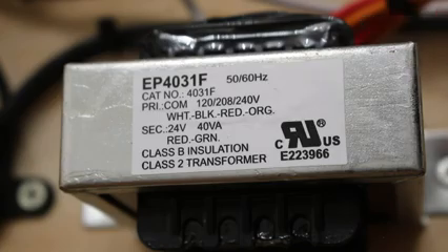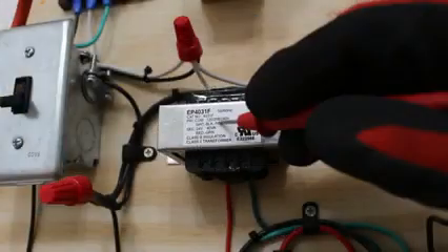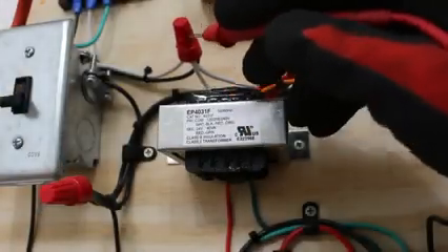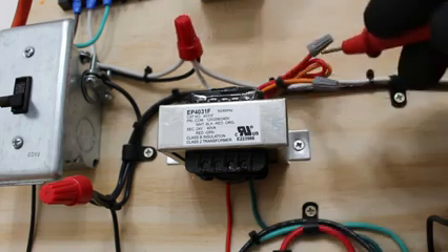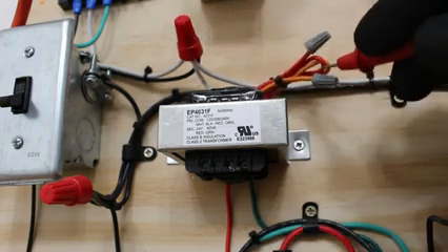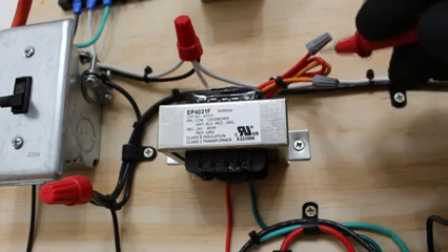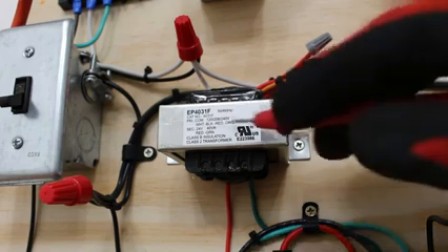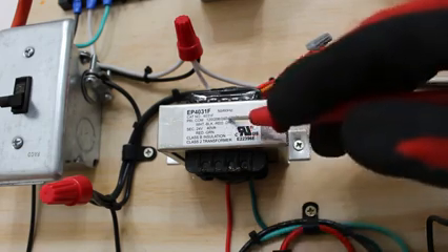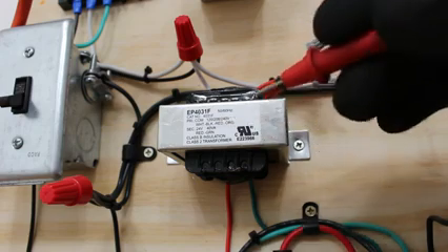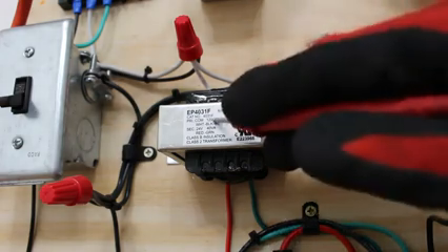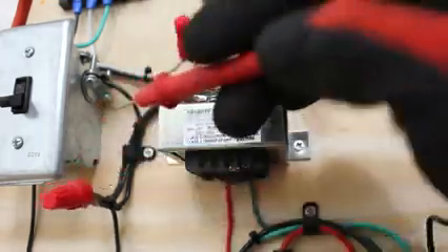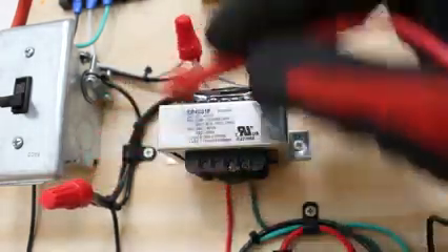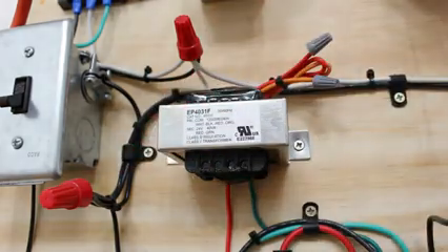So now let's trace out the wires. Okay, coming out, here I see my white, this is my common. But what do we have here? The red and the orange is capped off, so that means we're not using that. The red is 208 and the orange is 240. So now we know we're using our 120 volt circuit, because if I follow this again, here's my black wire. So between black and white, we should have 120 volts.